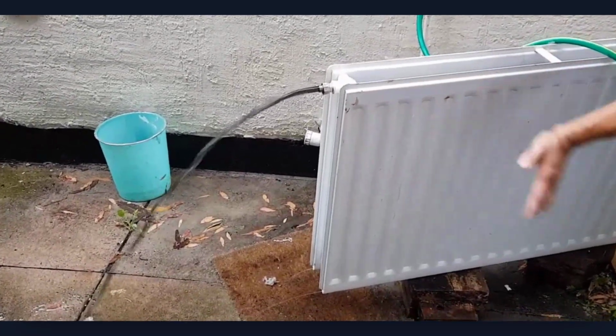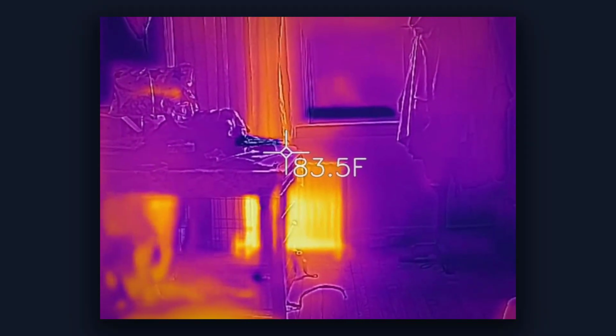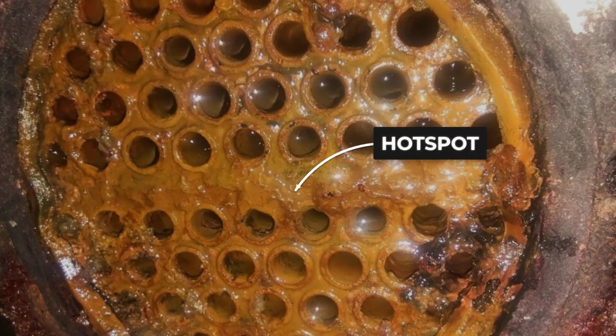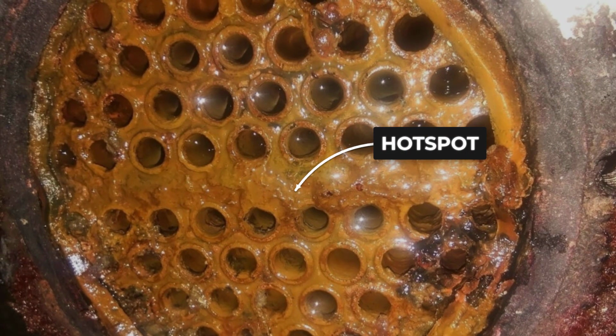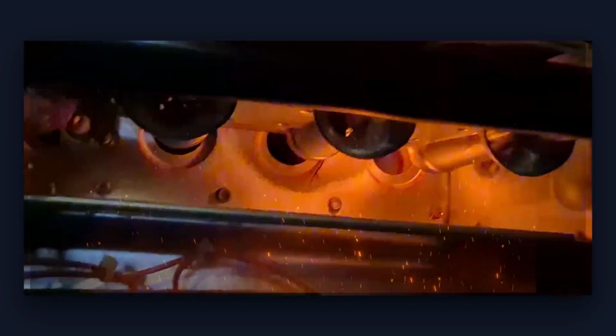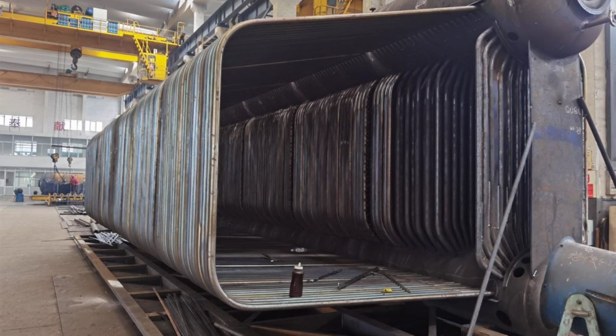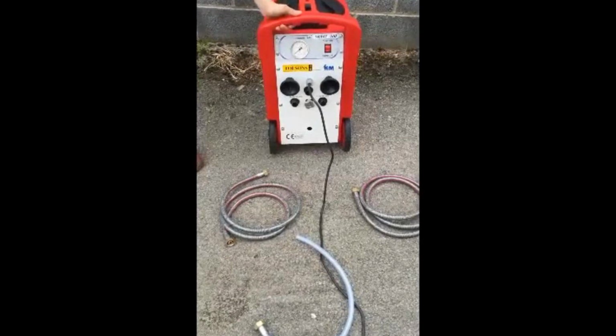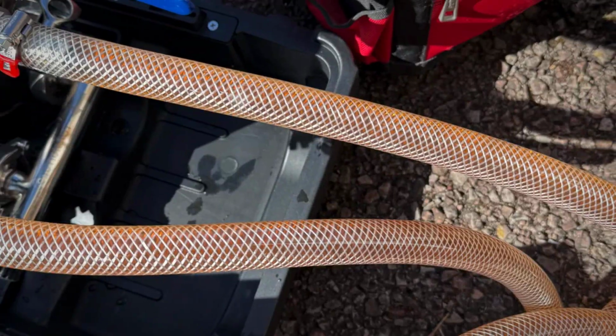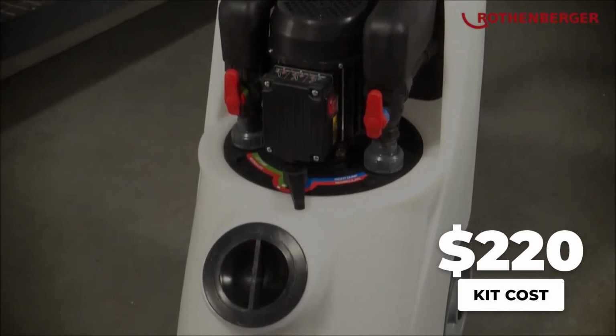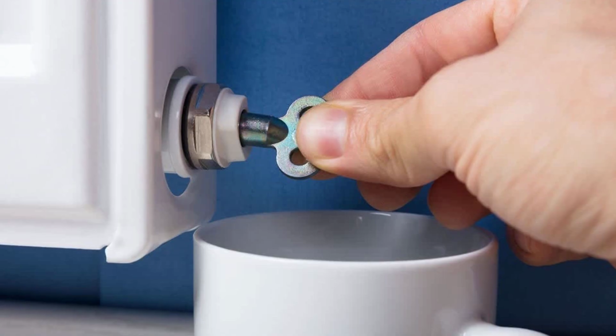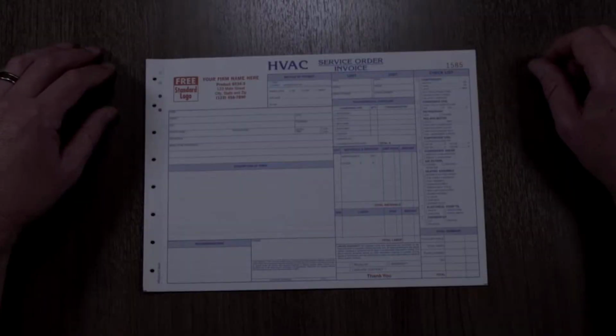That sludge settles in low spots, chokes off heat transfer, and creates cold patches on your radiators. Worse, it bakes onto the heat exchanger, causing dangerous hot spots that warp metal and eventually crack the core. The industry calls it normal wear, but it is manufactured neglect. A power flush is a hard reset. Specialized pumps blast water and cleaning agents through every inch of pipe, scouring out years of black muck in a single afternoon. For the DIYer, power flush kits run about $220, less than a single service call. Hire a pro and you are looking at $450 to $800, including labor and chemicals.